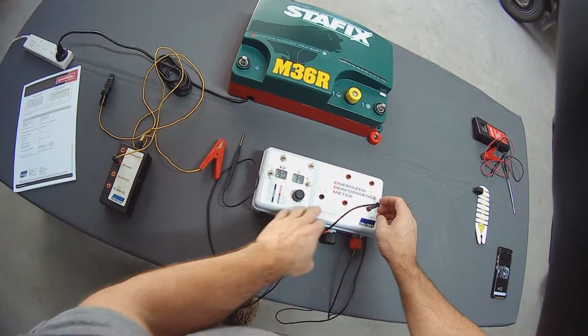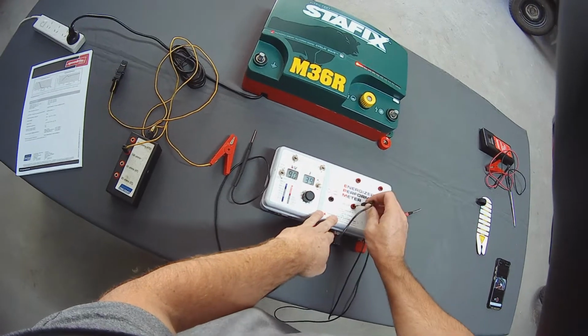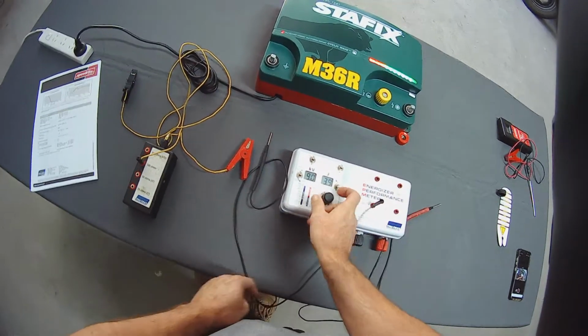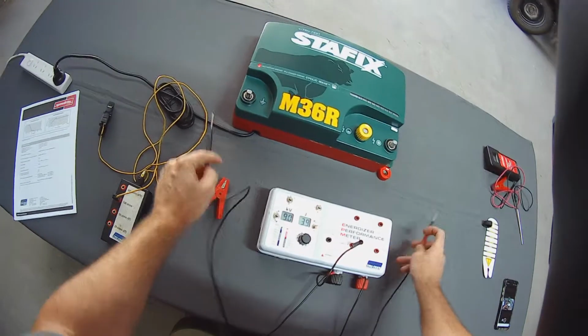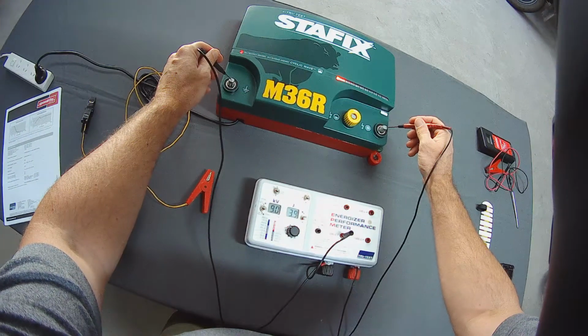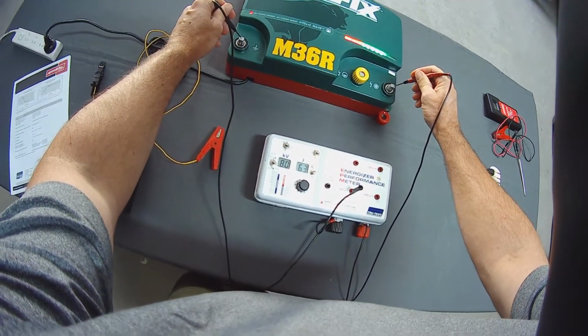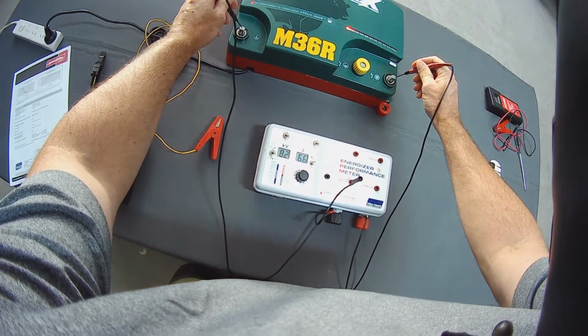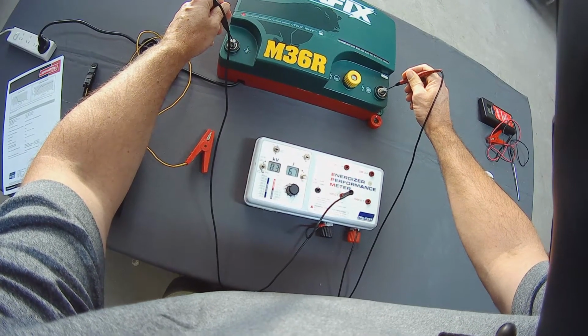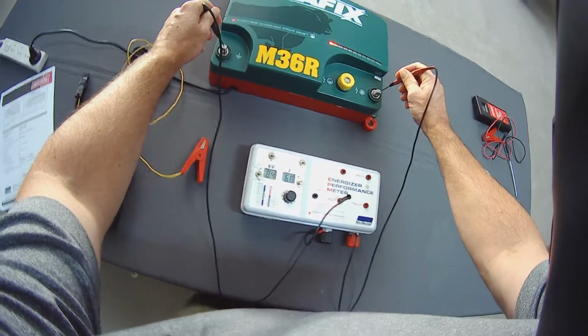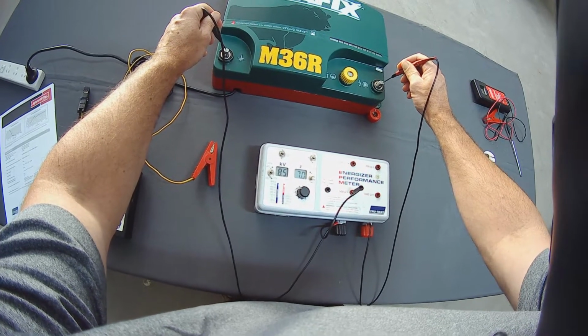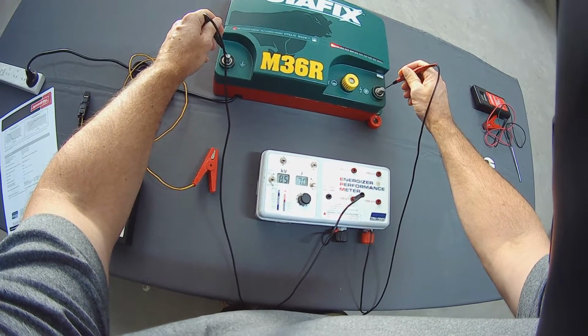If we then apply more load, if we go to 500 ohms, our probe goes in the 500 ohm port, our dial goes to 500 ohms. Once again on the terminals, reading now goes to 8.2 kilovolts with 6.6 joules. 8.3. So the Energiser is sensing the extra load. The joules has gone up. We're on to 7 joules. We're 8.5. And that's where it's sort of settled.